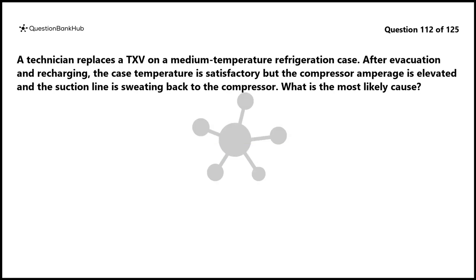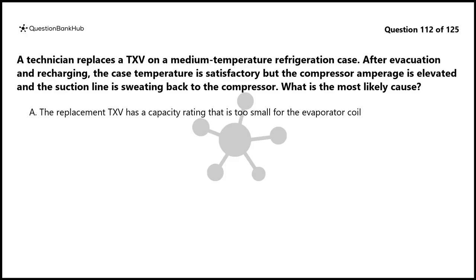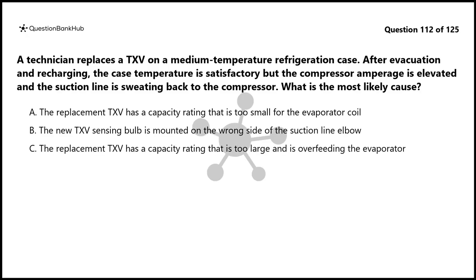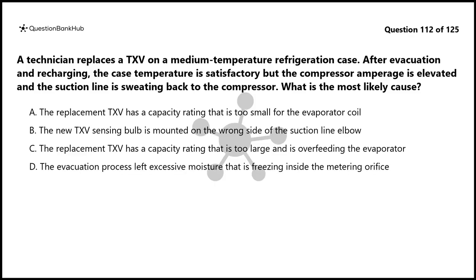Question 112. A technician replaces a TXV on a medium-temperature refrigeration case. After evacuation and recharging, the case temperature is satisfactory but the compressor amperage is elevated and the suction line is sweating back to the compressor. What is the most likely cause? A. The replacement TXV has a capacity rating that is too small for the evaporator coil. B. The new TXV sensing bulb is mounted on the wrong side of the suction line elbow. C. The replacement TXV has a capacity rating that is too large and is overfeeding the evaporator. D. The evacuation process left excessive moisture that is freezing inside the metering orifice.